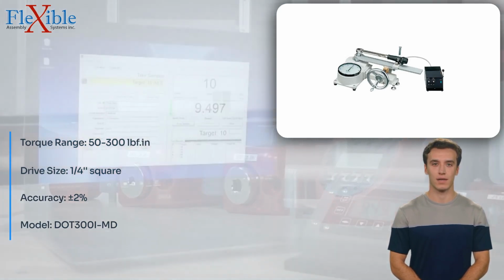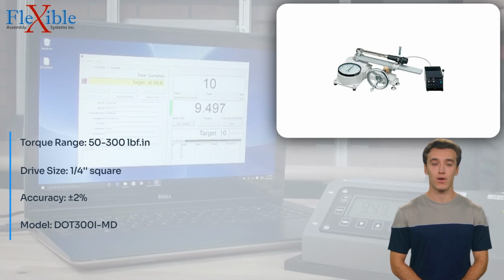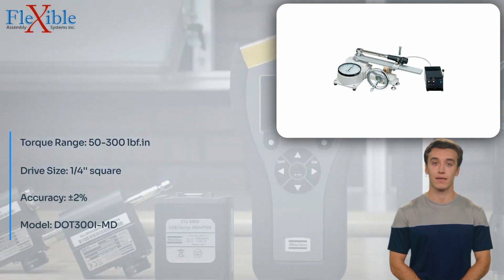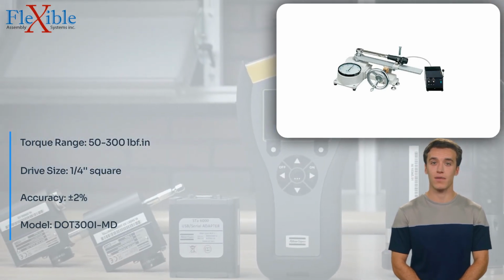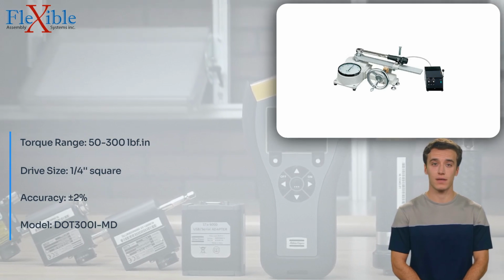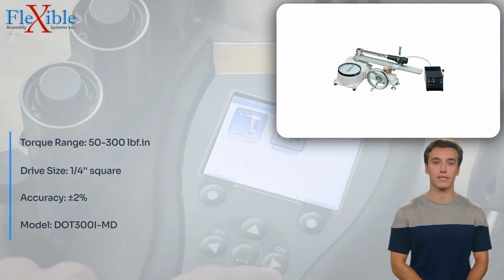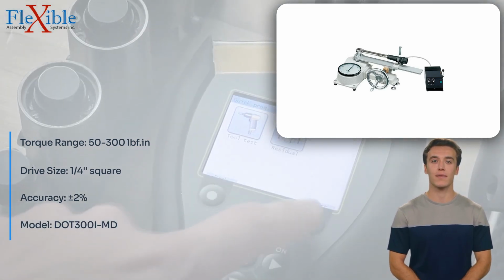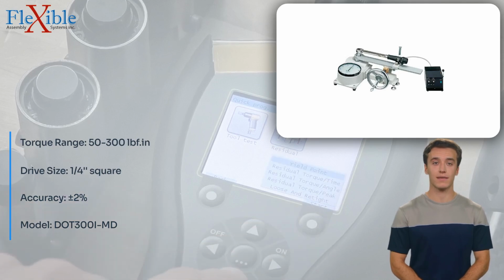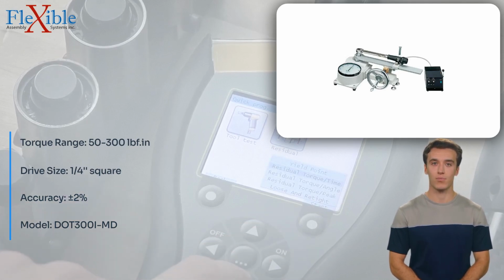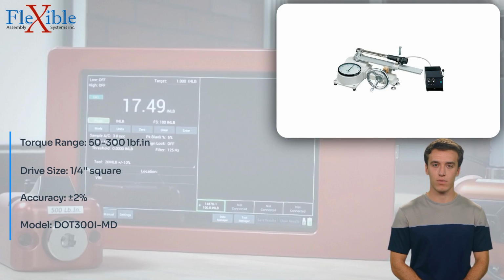The large and easy-to-read dial face offers clear and precise readings, allowing for accurate torque measurements. Designed to be set horizontally, the DOT300I-MD eliminates the need for weight correction, further simplifying the calibration process. Featuring a conveniently designed handle, this tester enables effortless torque wrench calibration with just a simple rotation.